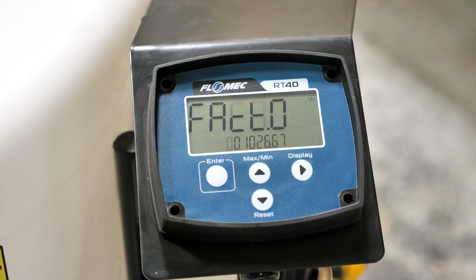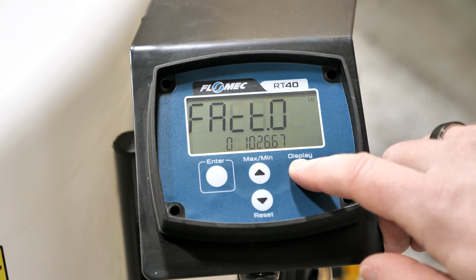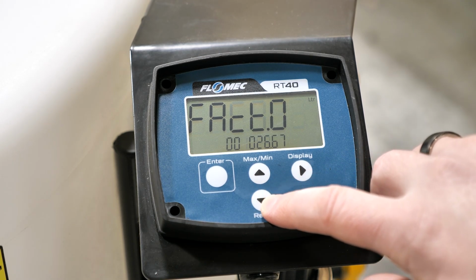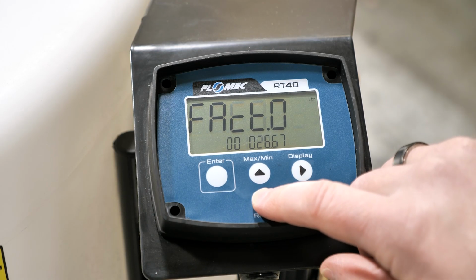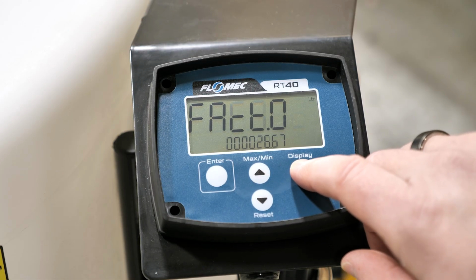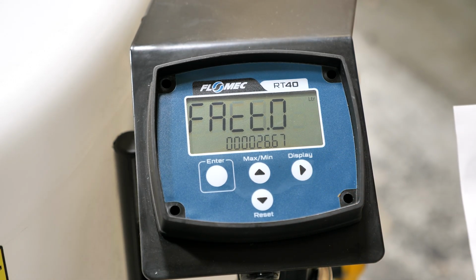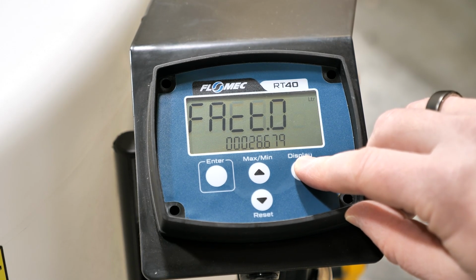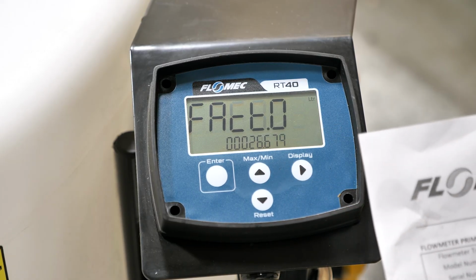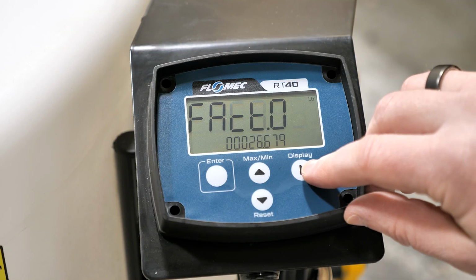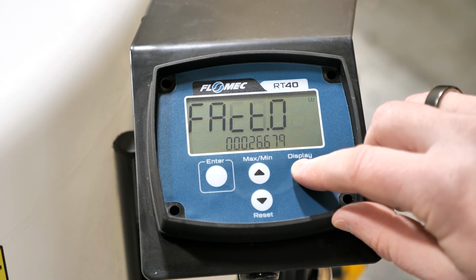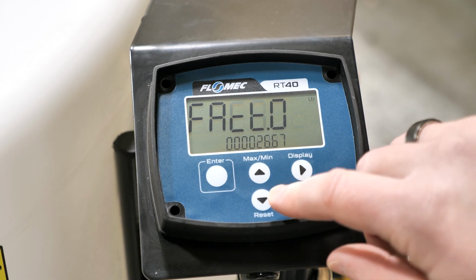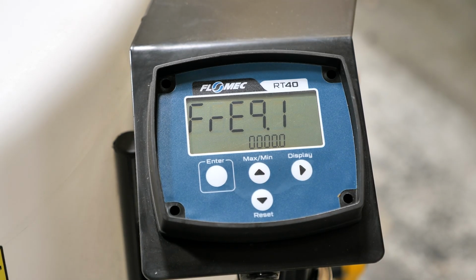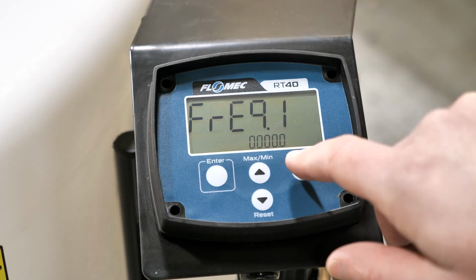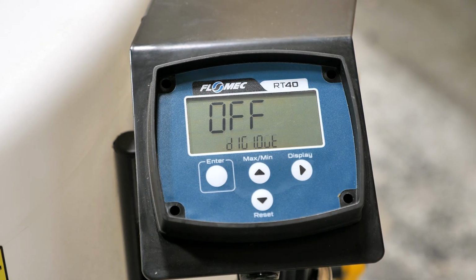And then in here, you can see we have a K factor in there already. But to put it in there, we're going to just go through the units. We're going to set it to that K factor that was on our specification sheet. So we're going to change this to a 0. The next digit is 26.67. And if you keep scrolling over, you'll get more decimal points. So you want to make sure you put in every single decimal point that is on your sheet. So in our scenario it is 26.679, and we are at 26.679. And then we're going to hit enter to go through there. So now we're at the next frequency of 9.1. We want that frequency to be 0, and we're going to hit enter.